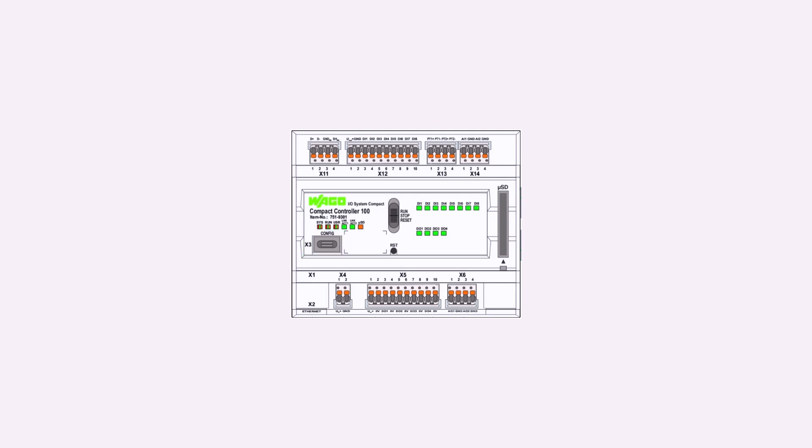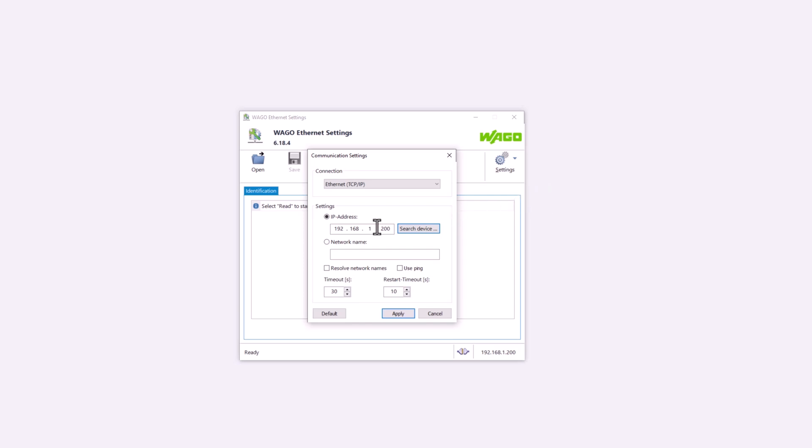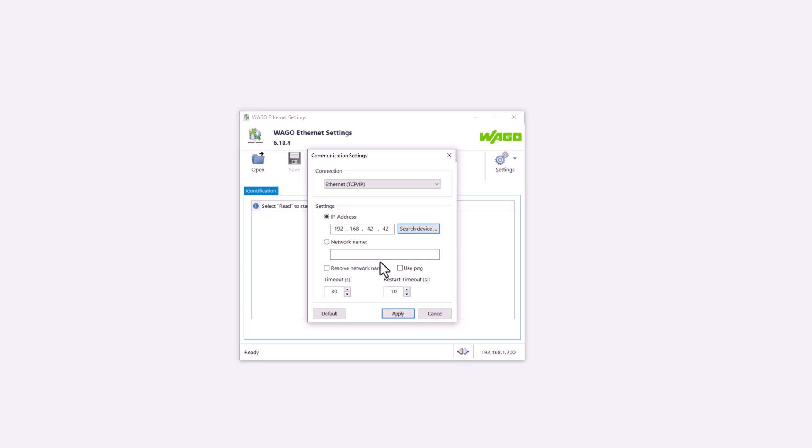As an example of a controller with a USB-C interface, we have a CC100 connected to a PC with a USB-C cable. Now we start the controller and once it has booted up, we open the Ethernet settings. Now select the Ethernet TCP IP connection. The IP address of the controller on the USB port is 192.168.42.42.